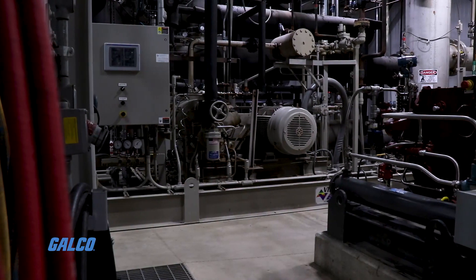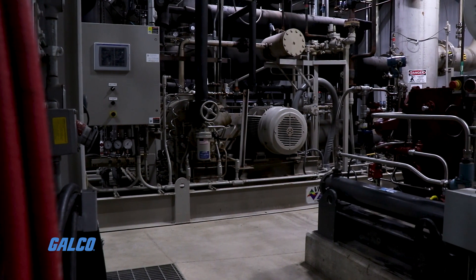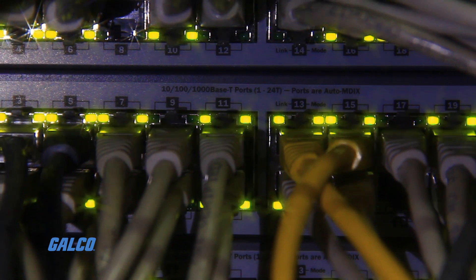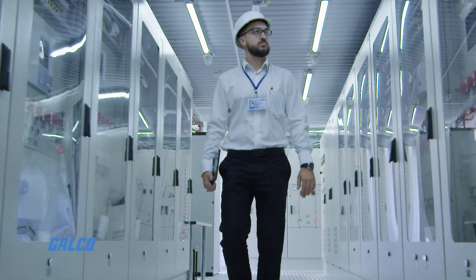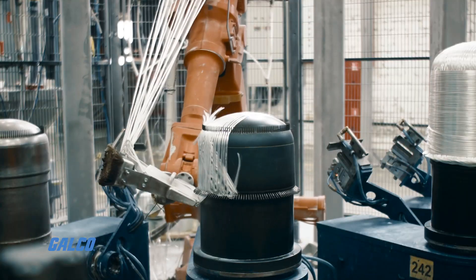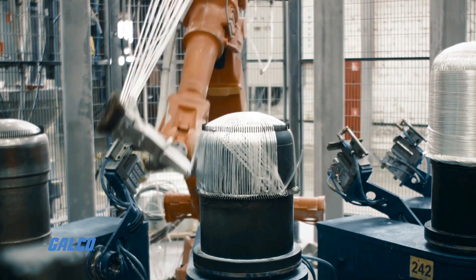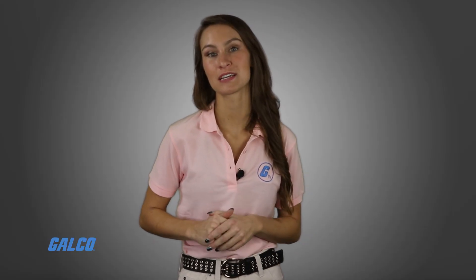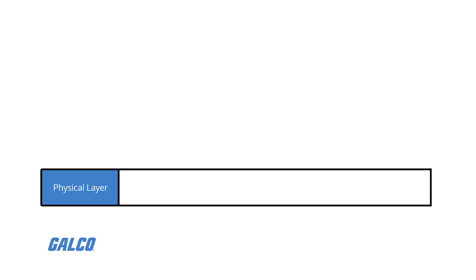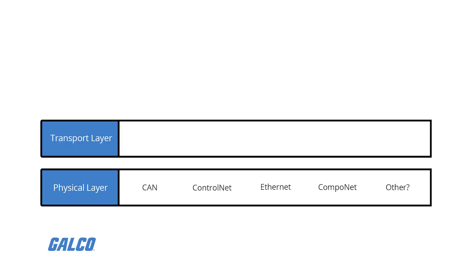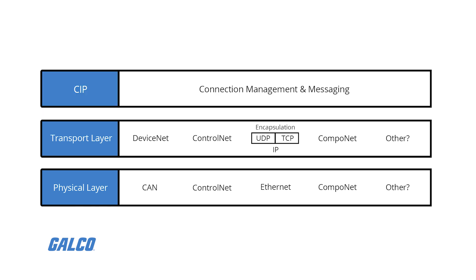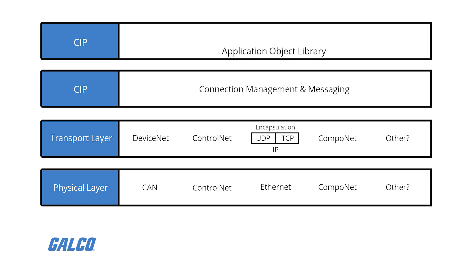Common Industrial Protocol is used by EtherNet/IP, DeviceNet, CompoNet, and ControlNet industrial network architectures. Where communication protocols like DeviceNet define the lower layers of an industrial network, like physical connection and data transfer instructions, the CIP manages the upper layers of the network.